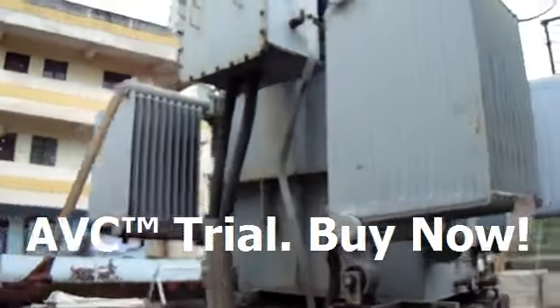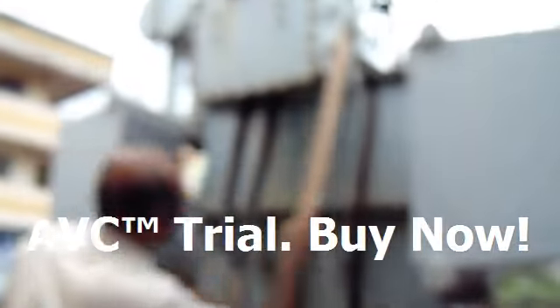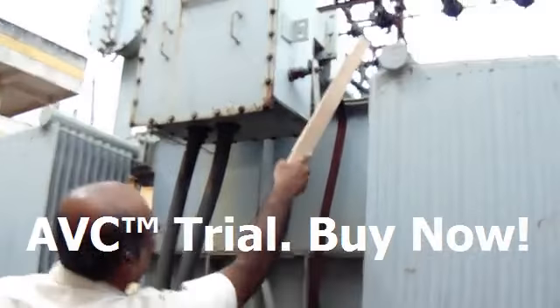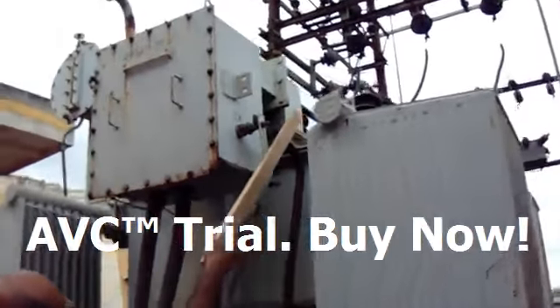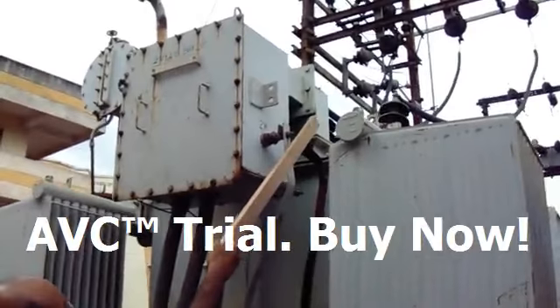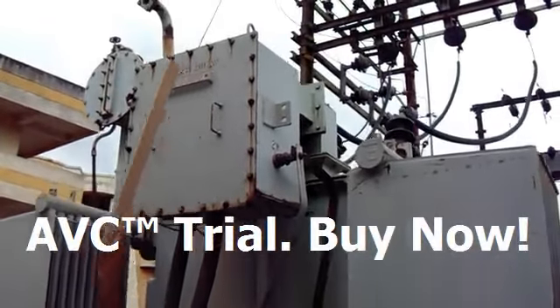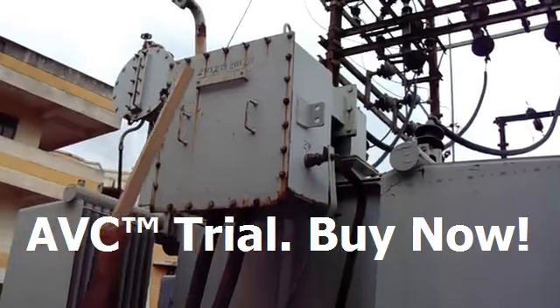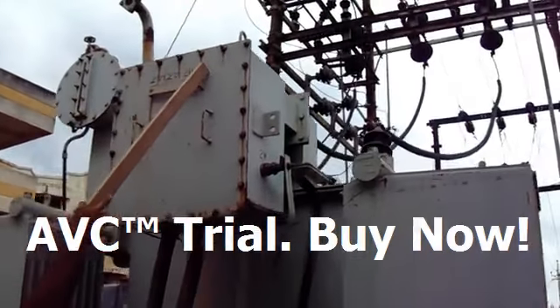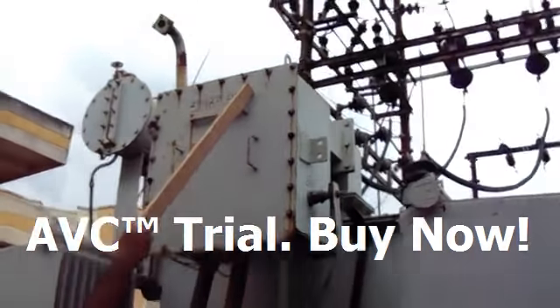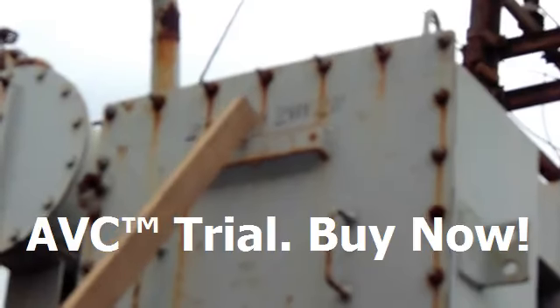you can see that on the LT side you will have this one indicating your neutral, and then the R phase, then the Y phase, and then the B phase. You can see that 2N stands for the neutral on the LT side, 2U1 stands for the R phase, 2V1 stands for the Y phase, and 2W1 stands for the B phase.